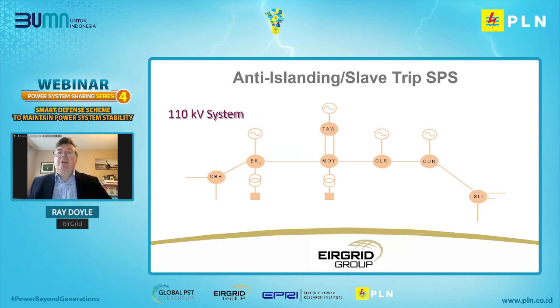I want to talk briefly about measures we put in to deal with anti-islanding and slave tripping. This is a small section of 110 kV network, where we have multiple two-line stations in a row. During maintenance combinations, or if two lines were to trip together, various stations can become disconnected from the transmission system, and so they can become disconnected with local generation. Our strategy here is to put in schemes to shut these islands down quickly if they form. Move on to the next slide, please.